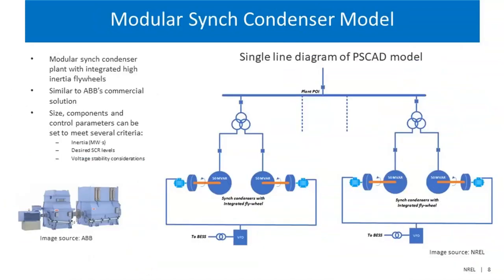Here is how we developed the model. This was actually, again, done in PSCAD. This is a simplified diagram. So it's a modular approach. We have a number of 50 MVAR synchronous condensers equipped with high-inertia flywheels, and they can be combined in a modular plant of any size, where you can actually set both inertia level, desired SCR levels at the point of interconnection, and also tune up your AVRs for desired voltage stability considerations. This is pretty much the approach adopted by ABB in their commercial systems, and one example of that system of high inertia synchronous condenser is shown on a photo.